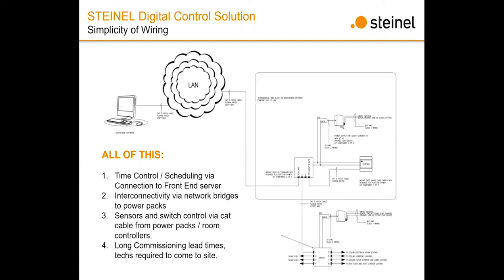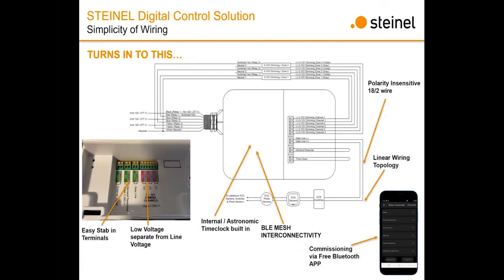All of that can be easily done with a single DCS. Again, there's an internal astronomic time clock on every single DCS, with every single relay being able to have its own sequence of operations. For example, if you have a DCS controlling two offices and a corridor, and only the corridor needs to have 9 to 5 functionality, we can absolutely do that. So you're not bound to a single DCS. You can actually be bound to a specific relay with that sequence of operations.